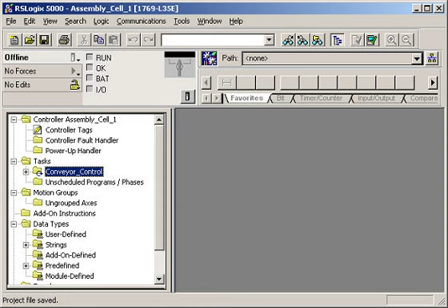In the Watchdog text box, type a timer value in milliseconds that specifies how long one scan of the task can take before triggering a major controller fault. Important: the time period must be longer than the sum of the execution times of all programs assigned to the task. After writing your program logic, you may want to review this value.